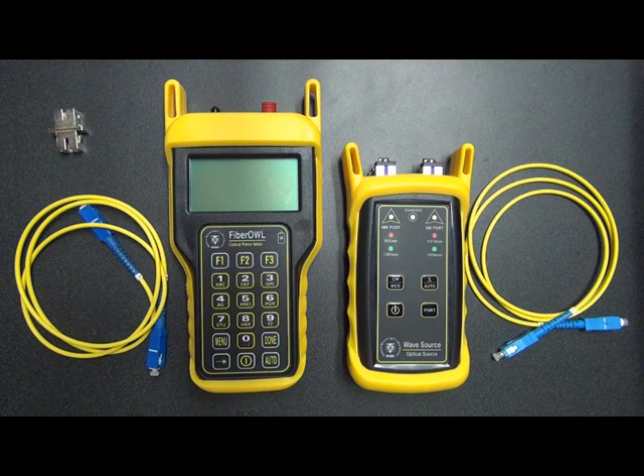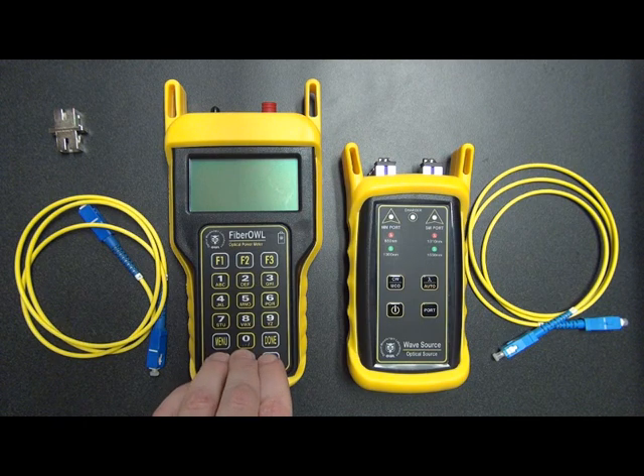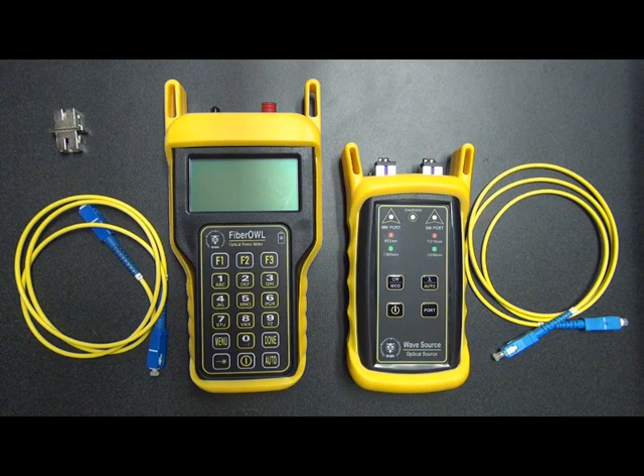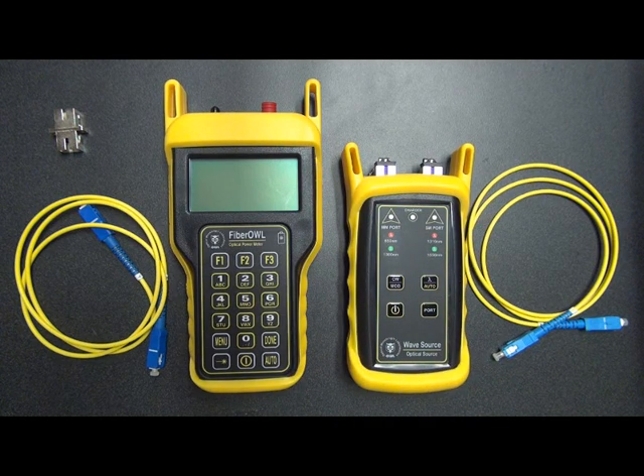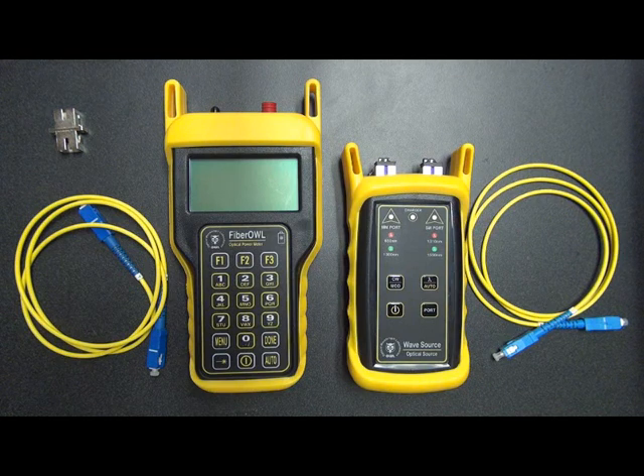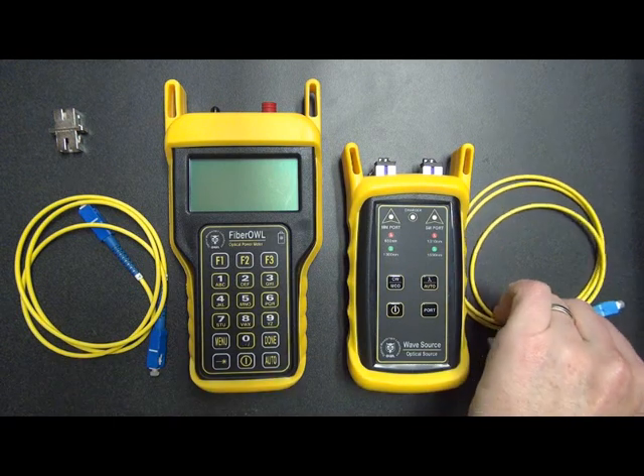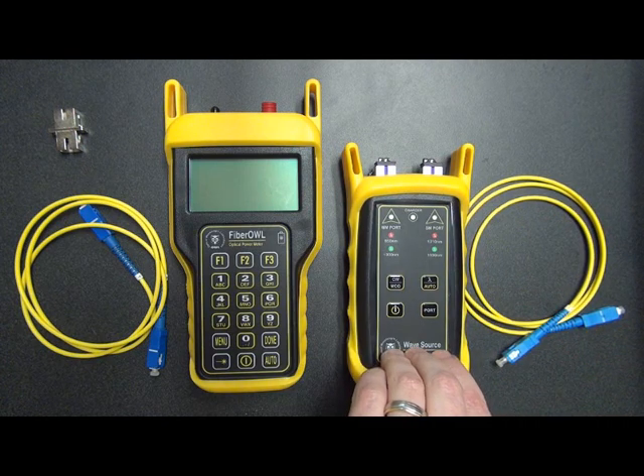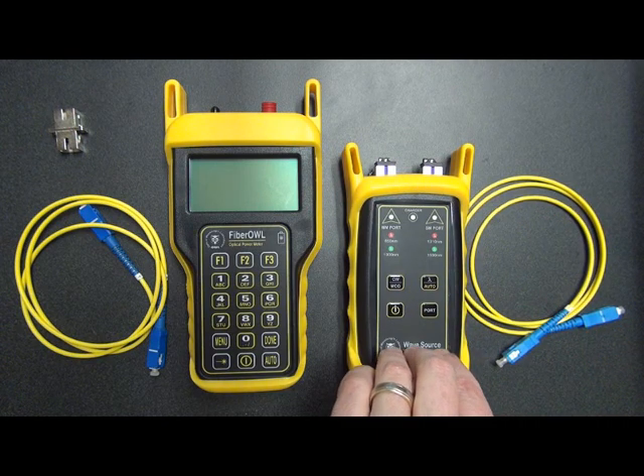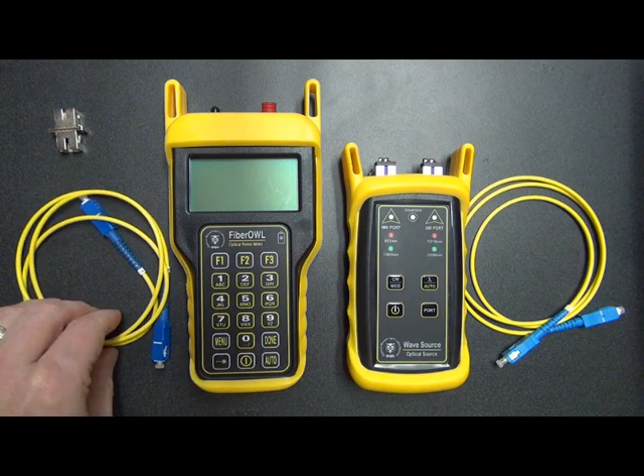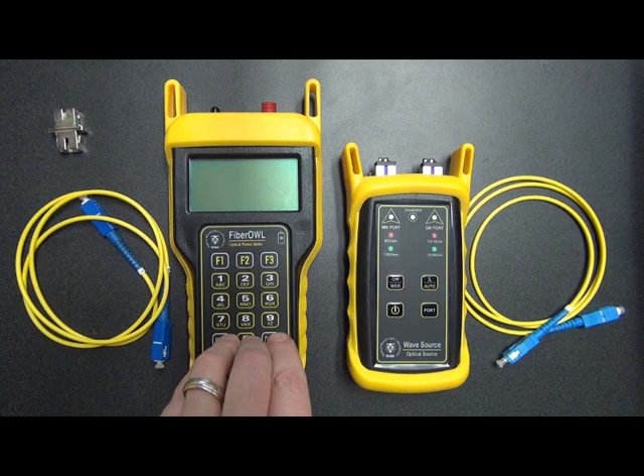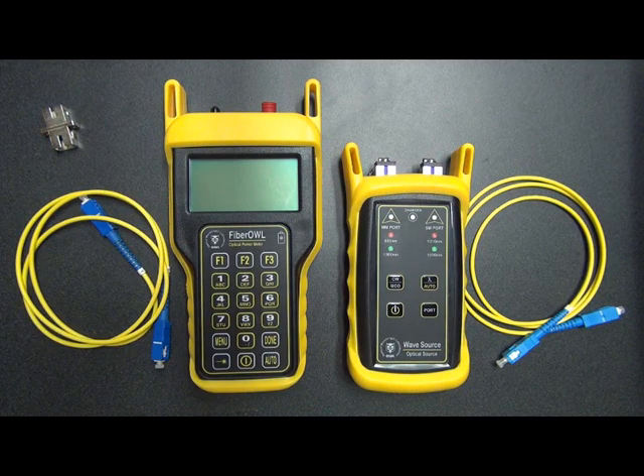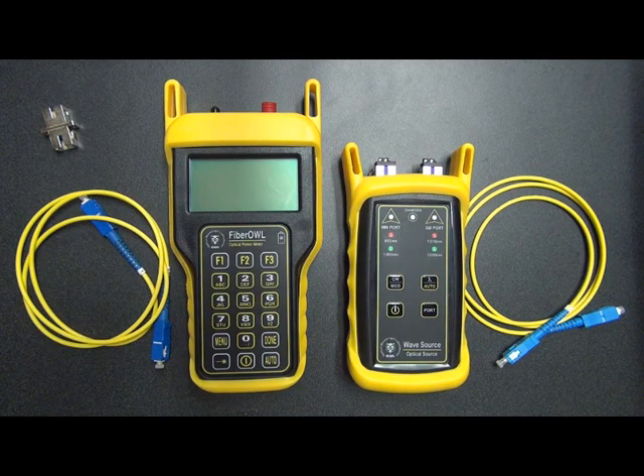In this procedure, we will be using a Fiber Owl 4 optical power meter and a single mode port and wave source light source. You'll notice that there are two patch cables and one mating sleeve used in this procedure. This reference cable will be used to connect the wave source into the link under test and also zero out the equipment together. This patch cable will be used to connect the Fiber Owl into the link under test, and the mating sleeve will be used to connect these two cables together for the purpose of checking them.